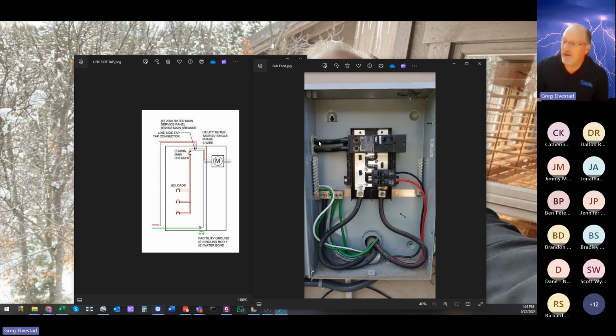I will put one caveat on this. Underwriter Laboratories will recertify a panel that has had these conductors intercepted to a junction box outside of the load center. I have yet to successfully arrange for one of those recertifications to occur because they want like $3,000 in fees to come and do that. That starts approaching the cost of a service entrance replacement. So just wanted to give you food for thought. If you want to explore that, just because there's sensitivity to a dwelling or some such thing that may prevent you from doing an upgrade, you may want to consider that. It's just an option.